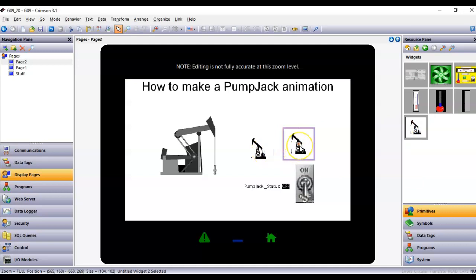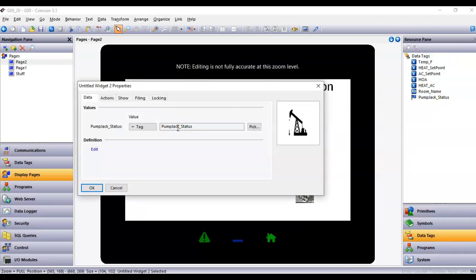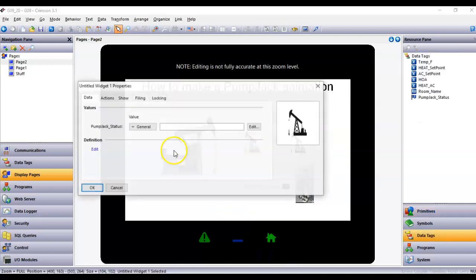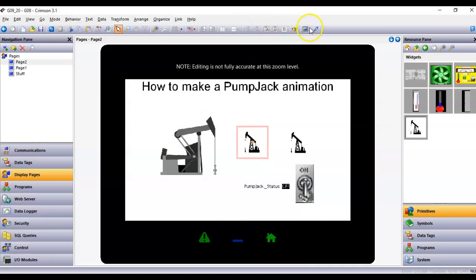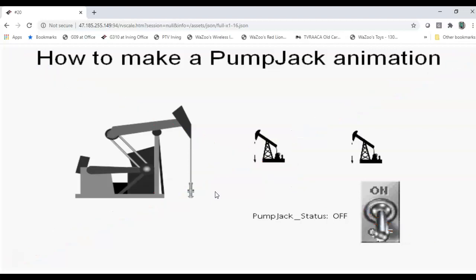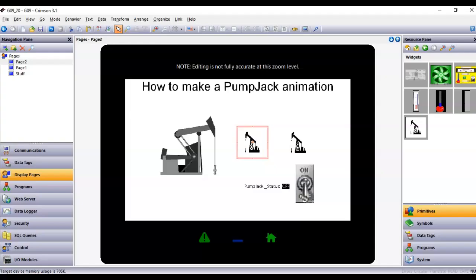I'll drag the widget out here alongside the original. I'll right-click on the widget instance, go to Properties, and drag in the pump_jack_status tag — which in theory should connect it to both the black off-state and the green animated one. My theory is this unconnected one won't work, but the widget will. After downloading to the screen, both show up. The widgetized one works correctly — turning it on and off behaves just as expected.